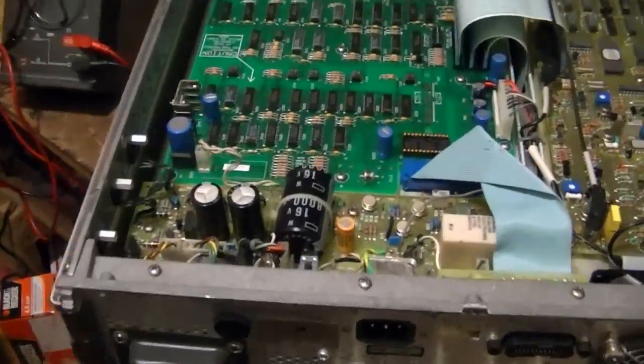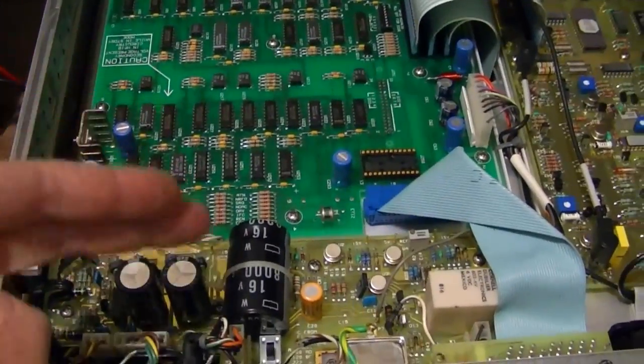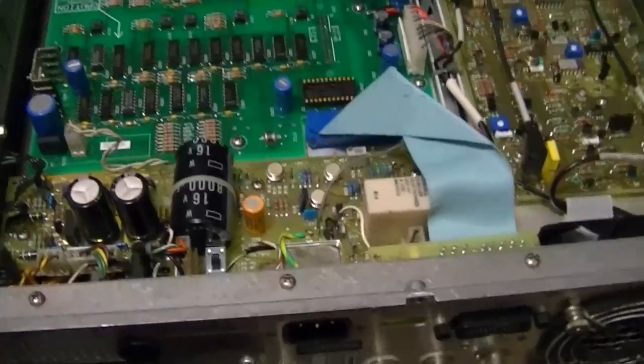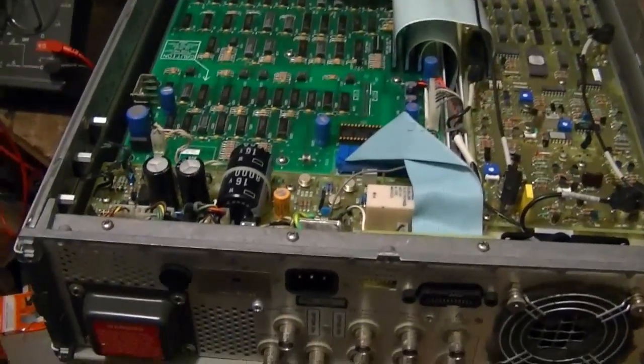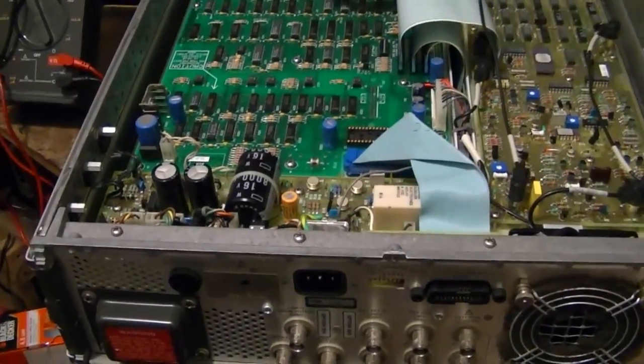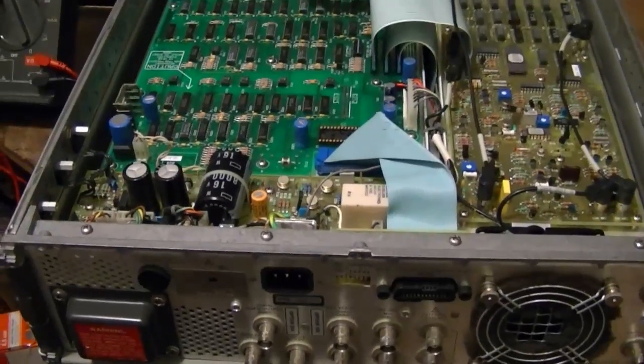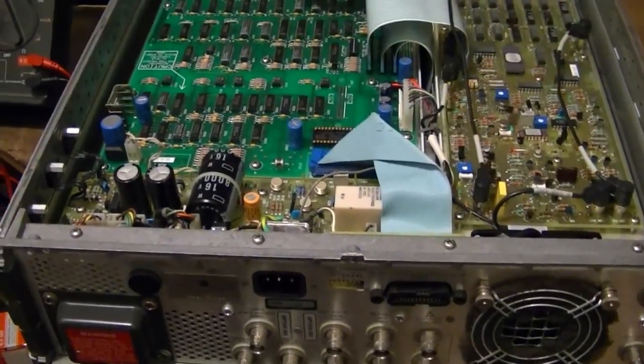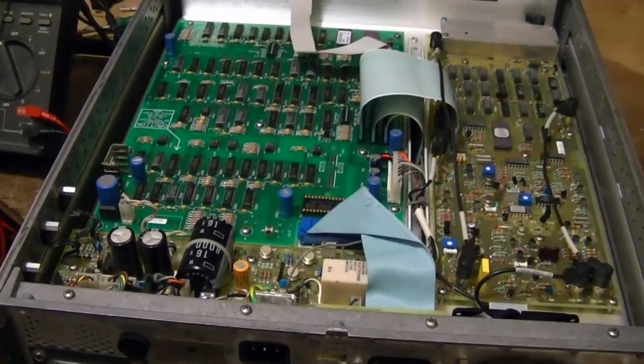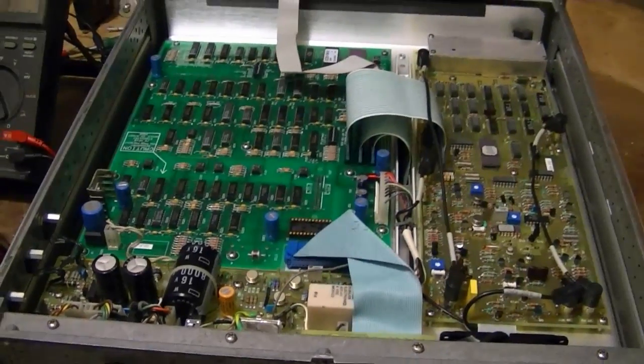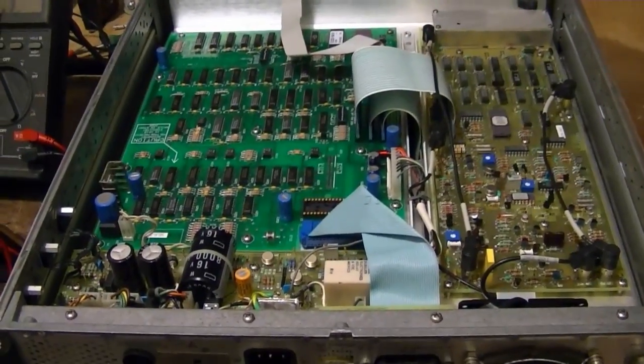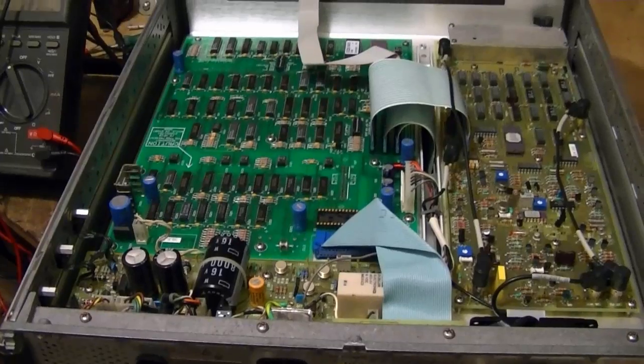Okay, I checked the voltages. +5 and ±15 dead on. Also went online and found all sorts of manuals. The owner's manual, the operator manual, the service manual, got schematics, got a partial parts list. What I don't have is a troubleshooting guide, so I couldn't find anywhere in those manuals to indicate what oscillator failure might mean.